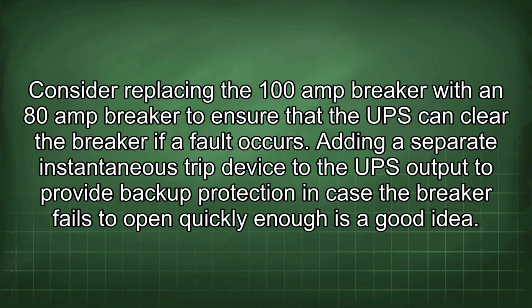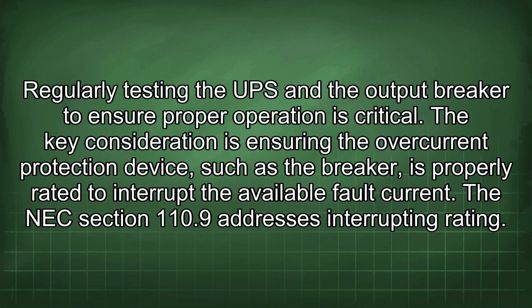Consider replacing the 100 amp breaker with an 80 amp breaker to ensure that the UPS can clear the breaker if a fault occurs. Adding a separate instantaneous trip device to the UPS output to provide backup protection in case the breaker fails to open quickly enough is a good idea. Regularly testing the UPS and the output breaker to ensure proper operation is critical. The key consideration is ensuring the overcurrent protection device, such as the breaker, is properly rated to interrupt the available fault current. The NEC section 110.9 addresses interrupting rating.